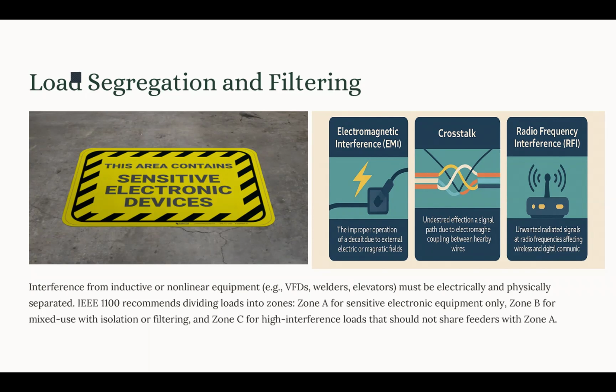The strategy that is defined in IEEE 1100 for segregation is defining three distinct zones based on the sensitivity to power quality and the level of interference generated by the equipment. We mentioned briefly those three zones. We have zone A, which is sensitive electronic equipment only. It has dedicated power distribution exclusively for those sensitive electronic equipment, like servers, medical imaging, or broadcast. We do not have shared circuits with inductive or nonlinear loads in this kind of system. The isolated ground bars are bonded directly to the signal reference grid.